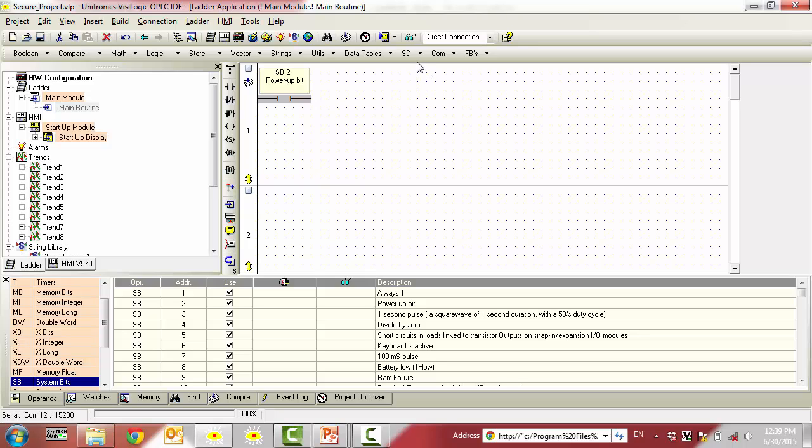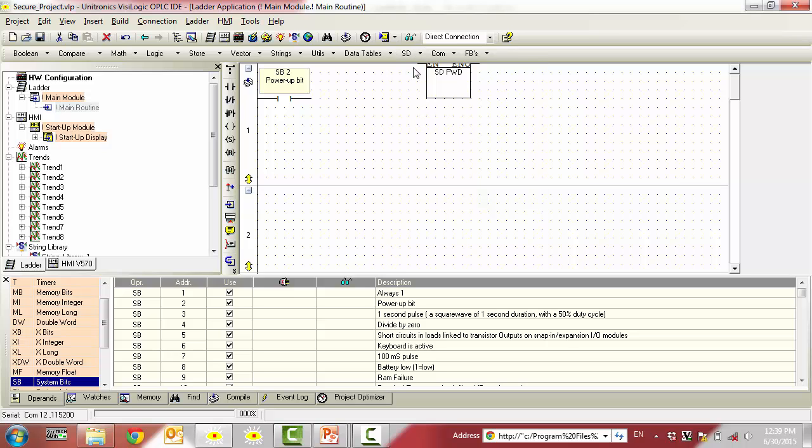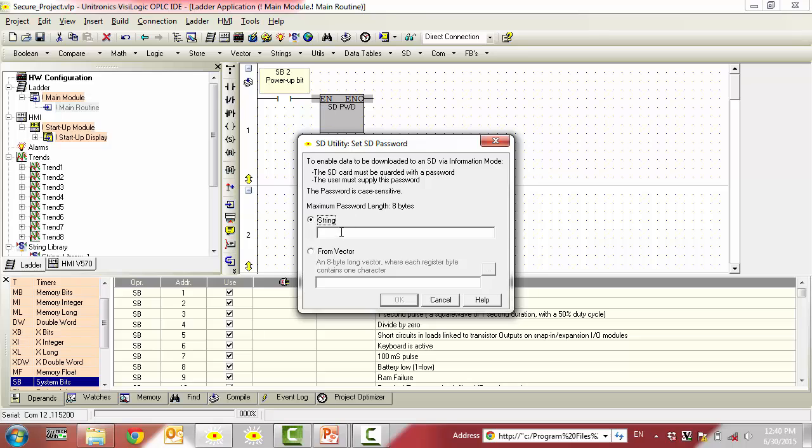Next, we want to go to the SD drop down menu. Note that this menu will only be available if you have a controller selected within the hardware configuration that supports SD card capabilities. Simply connect this to the PowerUp bit and provide an SD card password.